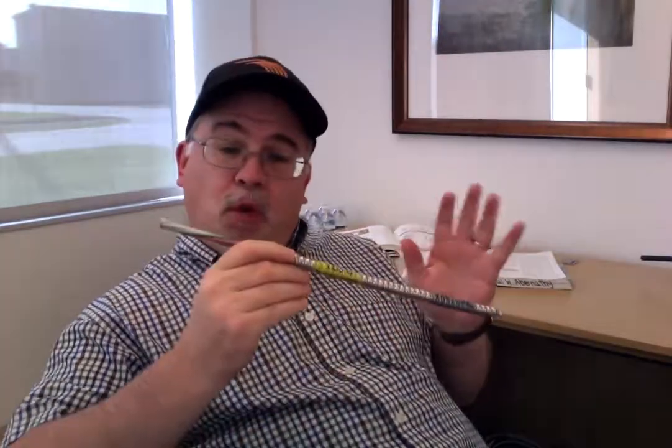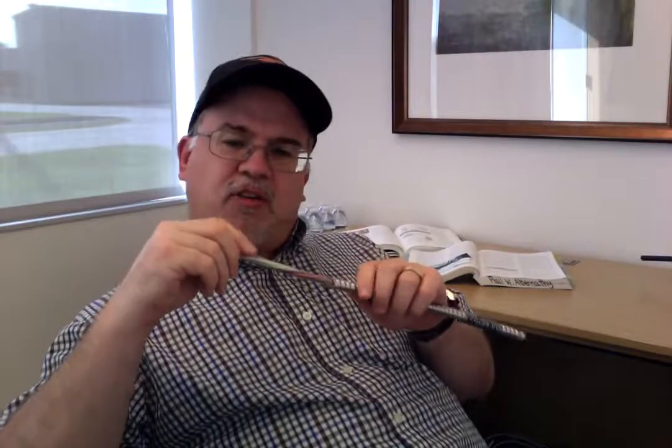All of that, depending on how you construct it and how you get it listed with UL, is basically your construction. So our typical normal type MC cable is going to have a polymeric wrap that goes around all the conductors. Now these conductors are cabled, meaning they're twisted together. Now, they're twisted prior to the armoring process.